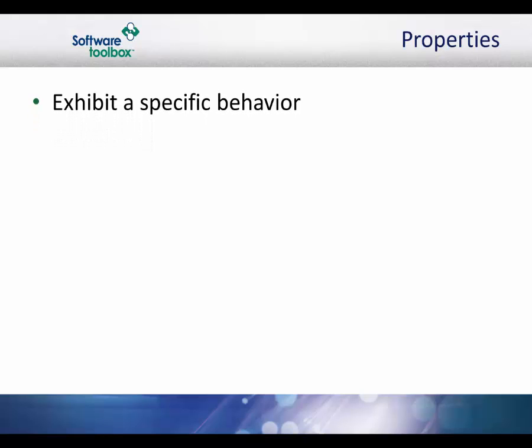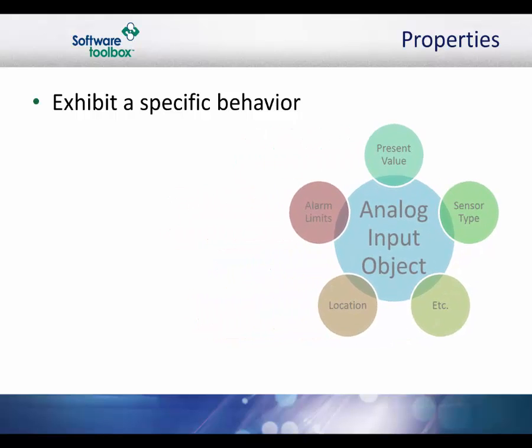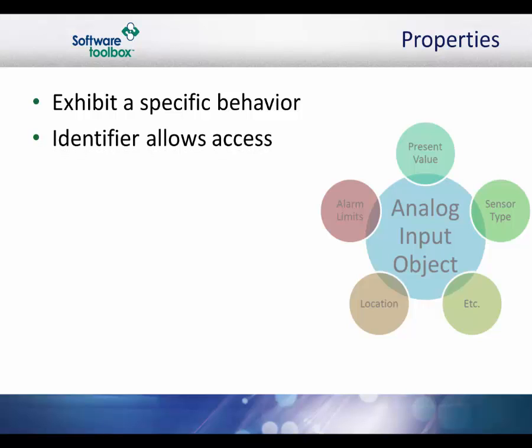Each property of an object has a specific behavior. For instance, each analog input is represented by a BACnet analog input object, which has a set of standard properties. These properties include things like present value, sensor type, location, alarm limits, and so on. Some of these properties are required, while others are optional. One of an object's most important properties is its identifier, a sort of numerical name that allows BACnet to easily access it. BACnet does allow vendors to add proprietary properties, but as with proprietary objects, the proprietary properties may not be understood or accessible by equipment from other manufacturers.